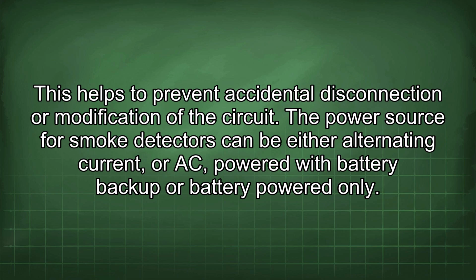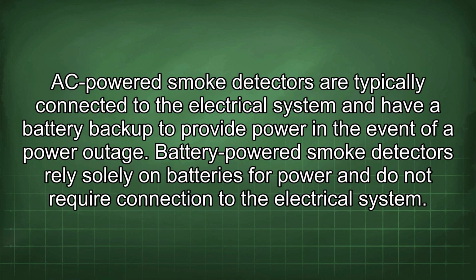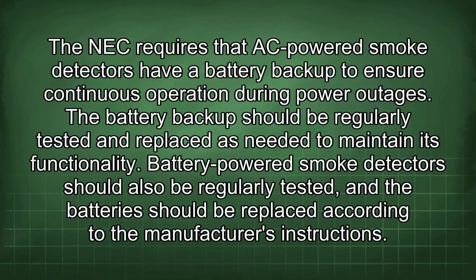The power source for smoke detectors can be either alternating current, or AC, powered with battery backup, or battery powered only. AC powered smoke detectors are typically connected to the electrical system and have a battery backup to provide power in the event of a power outage. Battery powered smoke detectors rely solely on batteries for power and do not require connection to the electrical system. The NEC requires that AC-powered smoke detectors have a battery backup to ensure continuous operation during power outages. The battery backup should be regularly tested and replaced as needed to maintain its functionality. Battery-powered smoke detectors should also be regularly tested, and the battery should be replaced according to the manufacturer's instructions.